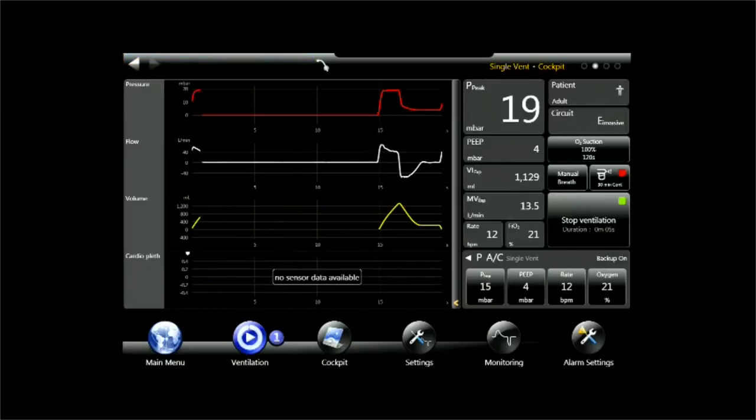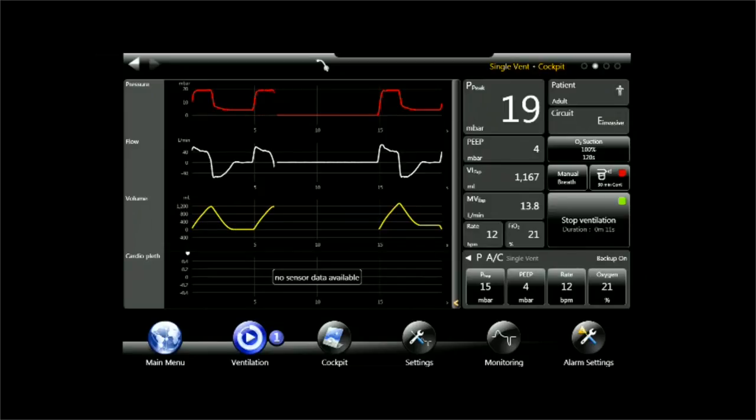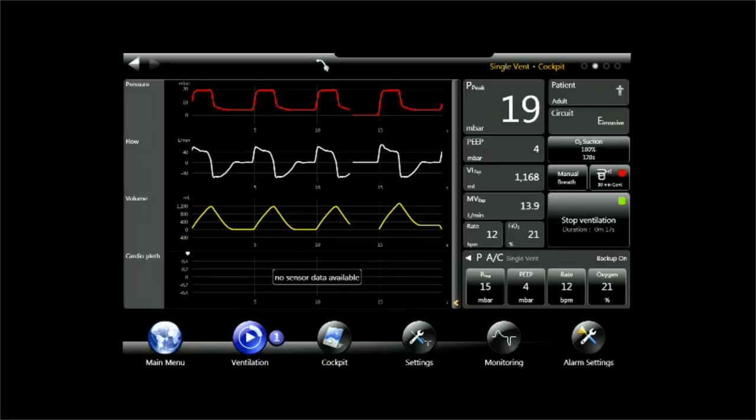So let's see if we receive any alarms. This is very normal that when we start with default alarm settings and default ventilation settings for a certain patient, it is very normal to receive alarms because each patient is individual and so is my test lung.